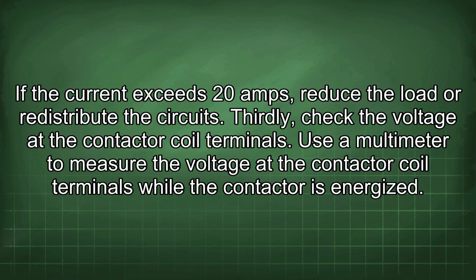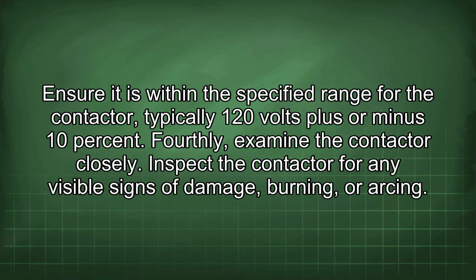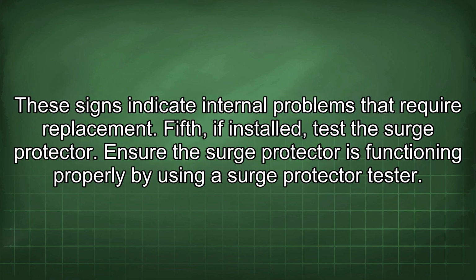Thirdly, check the voltage at the contactor coil terminals. Use a multimeter to measure the voltage at the contactor coil terminals while the contactor is energized. Ensure it is within the specified range for the contactor, typically 120 volts plus or minus 10%. Fourthly, examine the contactor closely. Inspect the contactor for any visible signs of damage, burning, or arcing. These signs indicate internal problems that require replacement.